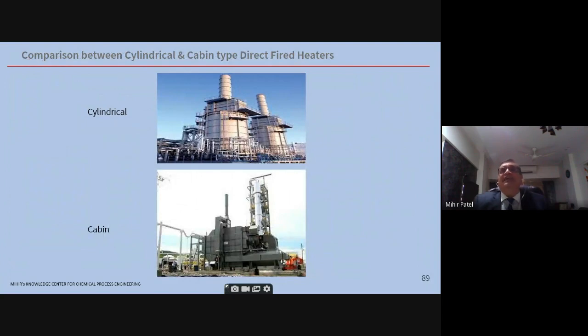So cylindrical type heaters occupy a smaller plot area, have larger sizes, lower cost, taller firebox, more draft at the burner, higher flue gas velocity in the convection section, so the gas film coefficient is higher because of that, and they can accommodate more parallel passes in the process coil. Now the cabin heater is shown at the bottom. It has a process coil that is easily drainable, two-phase flow problems are less severe, it can accommodate side end firing leading to the floor being nearer to the ground, and it is cheaper in smaller sizes. So this is the overview of the different types of heaters.